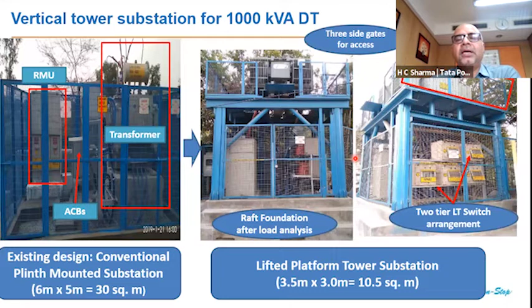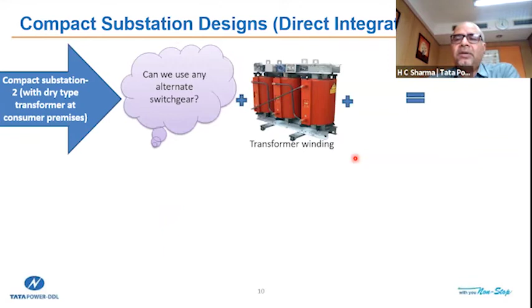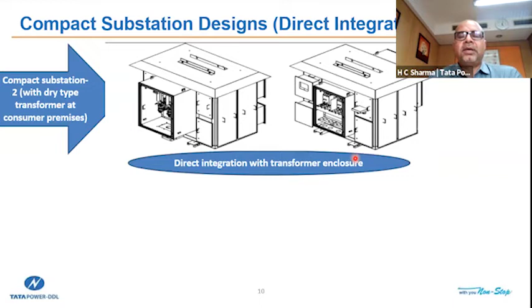The next initiative is the compact substation. Earlier, the RMU switching devices, the transformer, and the LT device were all separately placed. There were advantages to this, since separate placement made maintenance easier. But now we have made it a unitized substation, where this drawing shows all three components merged together into one unit, with switching on the HT side, switching on the LT side, and the transformer combined. This greatly reduces the space requirement.